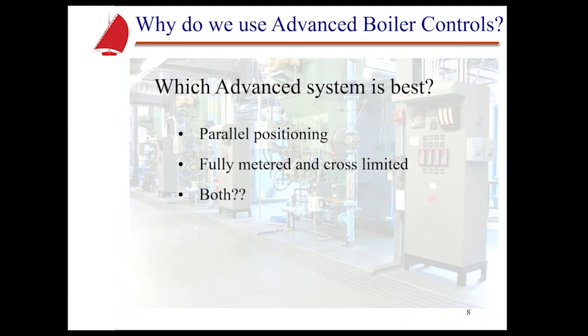That feedback from those servos is coming directly from usually a position potentiometer in the servo itself. Now, that works fantastic and has for many, many years. But we also have an option with fully metered and cross-limited, and you will hear those terms. In a fully metered cross-limited system, it's going to be using servos also, but the feedback is going to be from fuel flow meters and air pressure, for instance. So we make sure that we've got those points exactly based off of that feedback. And it's going to be cross-limited so that basically nothing gets way out of ratio.